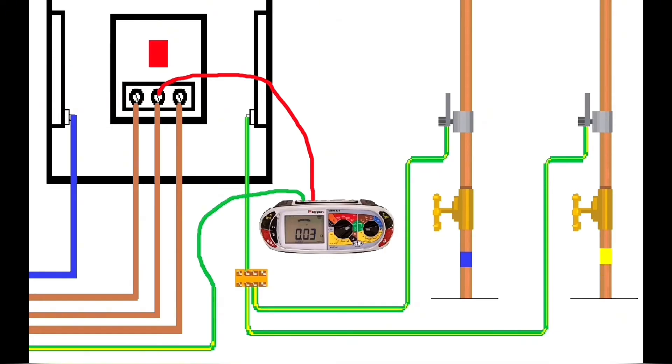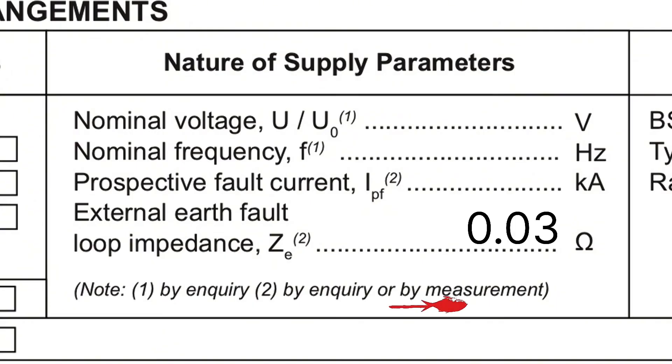It's the only live part within the board. I would test between the earthing conductor and L2, remember the reading, before I move on and test L3. Now my disconnected earthing conductor is tested, and I remember the highest of those three readings. The highest reading would be recorded.